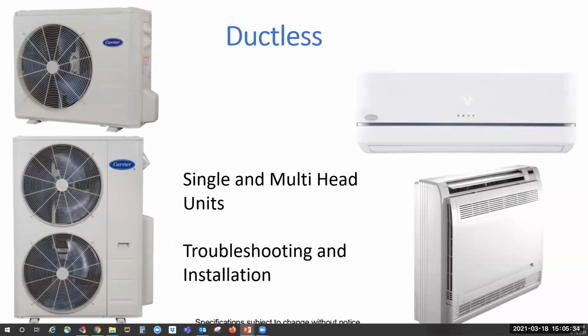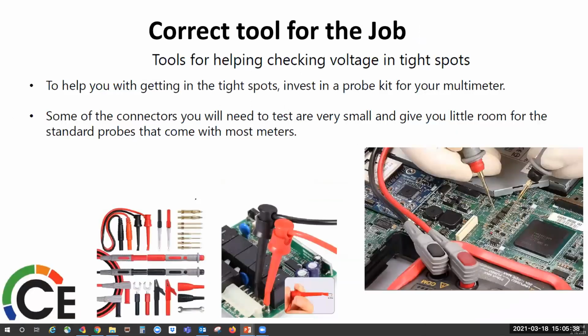Ductless single and multi-head units, troubleshooting and installation. Correct tool for the job: a good digital multimeter, capable of reading AC and DC volts. A megohm meter is a good idea, or a multimeter capable of reading megohms. Also, most manufacturers have small needle probes. This will help you get into the tight spots on the Molex plugs, and it's not just for the ductless. Our rooftops have them, furnaces have them, regular heat pumps and air conditioners all have these Molex plugs, which are really small. If you force your larger probes in there, you could damage something. We don't want to damage anything, just trying to do diagnostics.